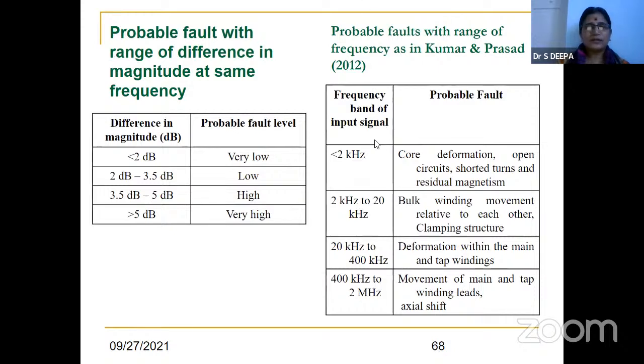There's a frequency band of input signal and the probable fault. If it is less than 2 kilohertz: core deformation, open circuit, shorted turns, and residual magnetism. 2 kilohertz to 20 kilohertz: bulk winding movement relative to each other, clamping structures. 20 kilohertz to 400 kilohertz: deformation within the main and tap winding. 400 kilohertz to 2 megahertz: movement of main and tap winding leads, axial shift. So this is the pattern.